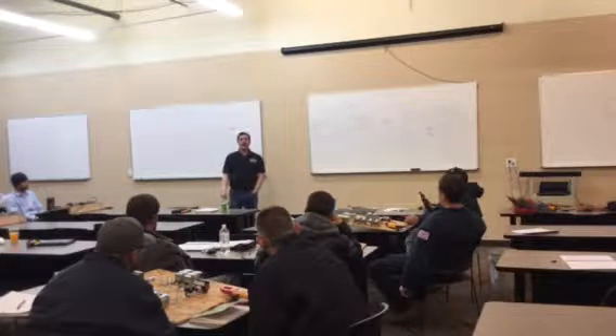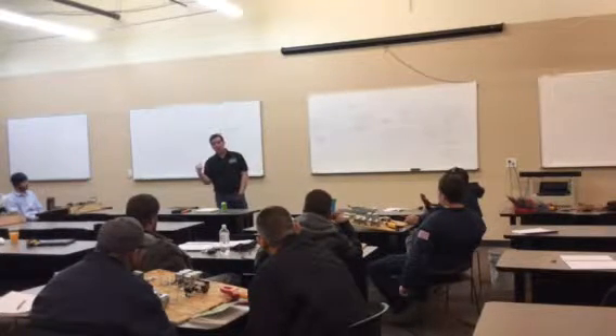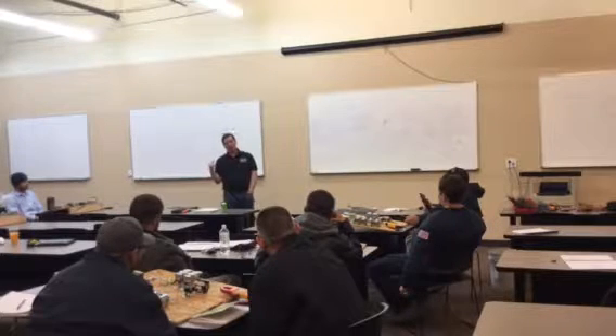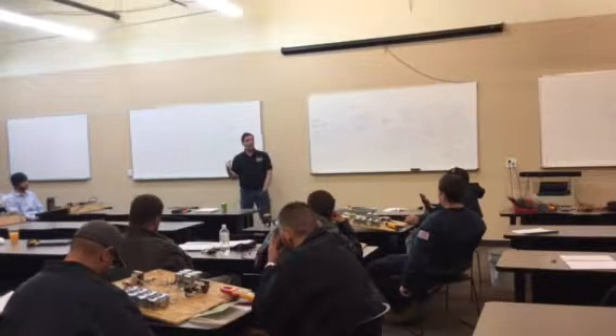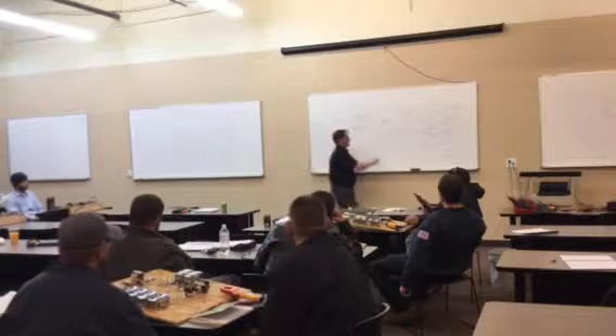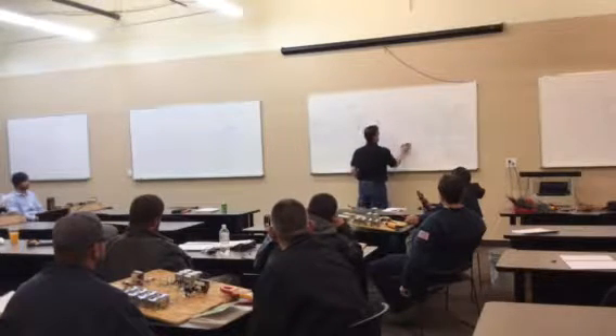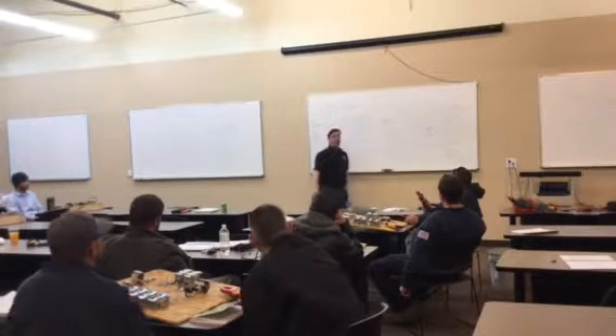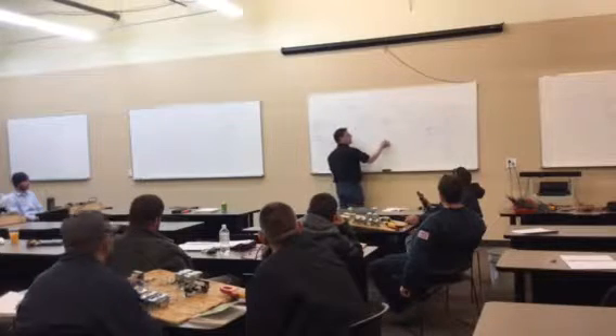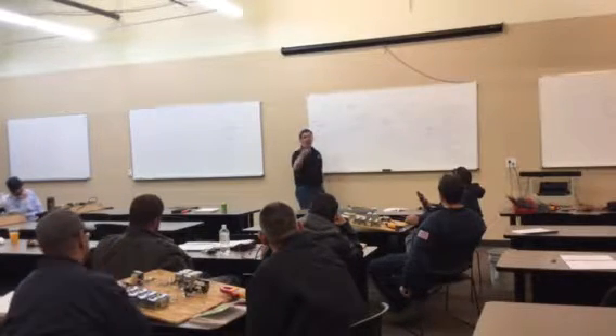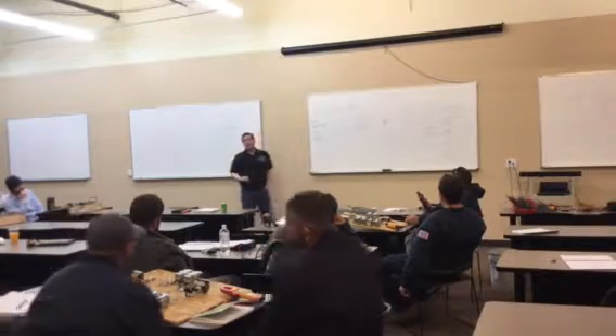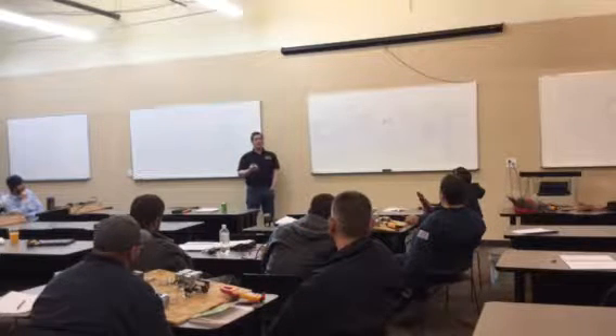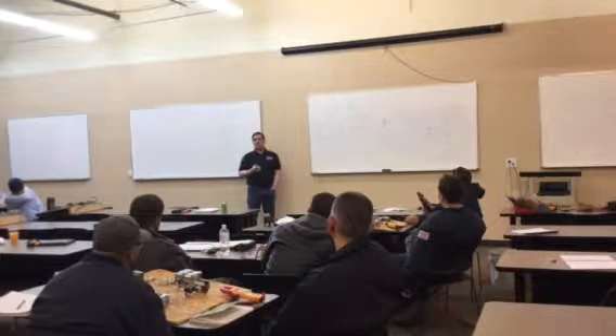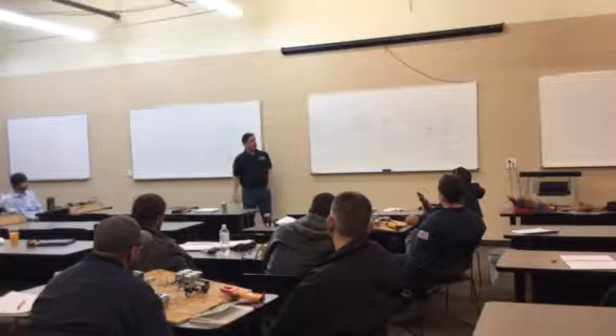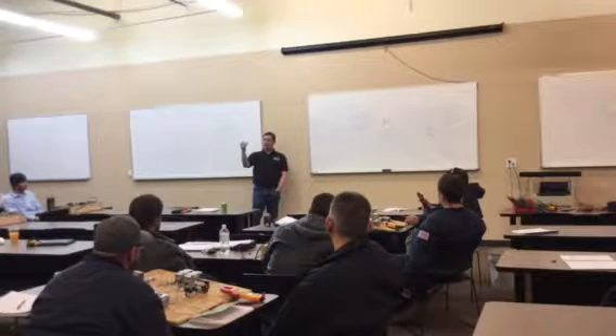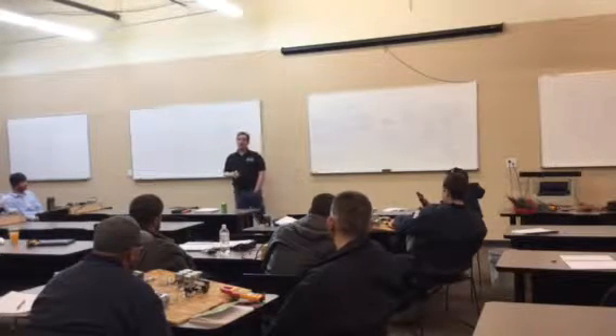Or when one of those things connected to it is having a problem, causing it to try and consume more power than it normally would, the result will be the transformer is unable to supply that level of power, and as a result, the voltage it puts out will drop. It will suck voltage literally right down, because it's putting out as much as it possibly can, and when it gets overloaded, its voltage will drop.